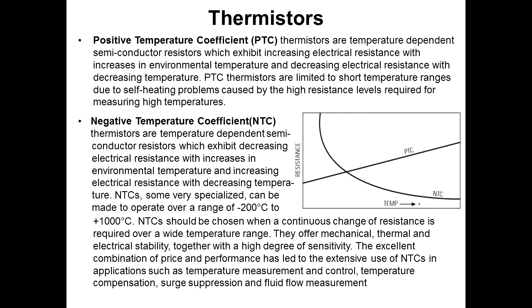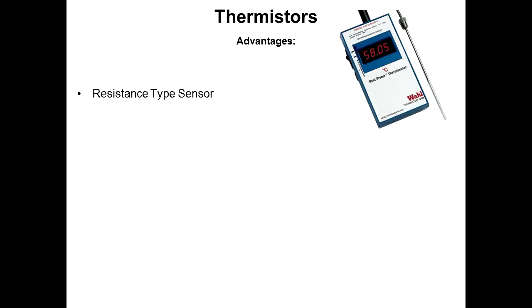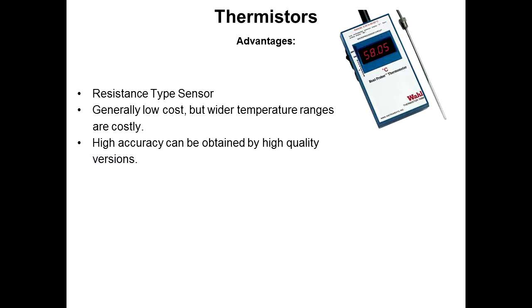Most common thermistors are good up to about 500 Fahrenheit. There are some specialty units out there made by Yellow Springs that you can take up to 1000 C. They're made with exotic metals. They're quite expensive, for specialized use. Thermistors are nonlinear and require some sort of microprocessor to linearize them to make sense of the reading. So the advantages: resistance type sensor, more accurate, lower cost, wider temperature ranges are more costly. High accuracy can be obtained with high quality versions. Good stability, much better than thermocouples, but the stability does increase with age as they settle in.